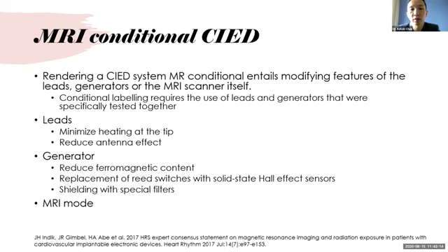So let's talk about the leads. Most pacing leads are coaxial in design. They have an inner and outer insulation and an inner and outer coil, delivering while maintaining flexibility and durability. The inner coils are wound three-dimensionally with a certain pitch or angle. Changing the geometry of these relationships by altering the number of filars or winding turns can change the propensity of the lead to act as an antenna, or the likelihood of efficient lead tip heating.